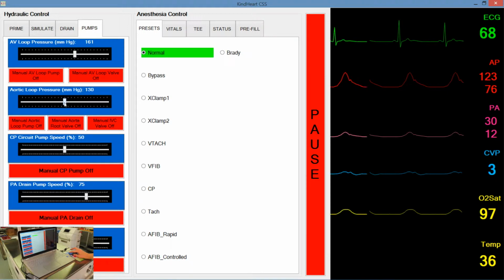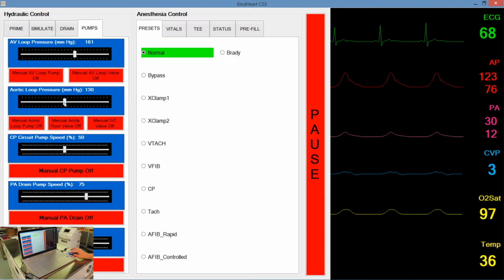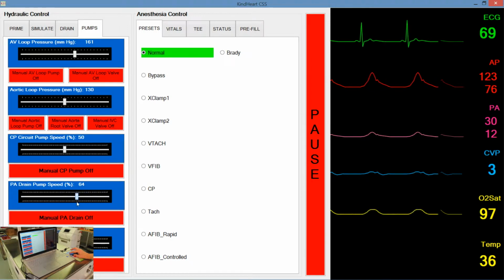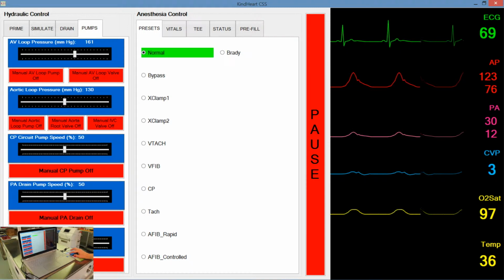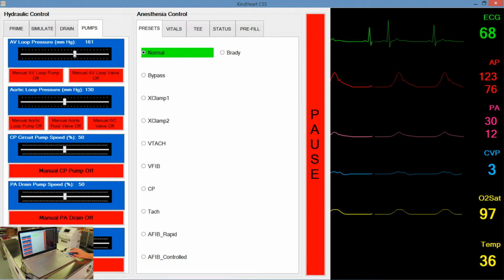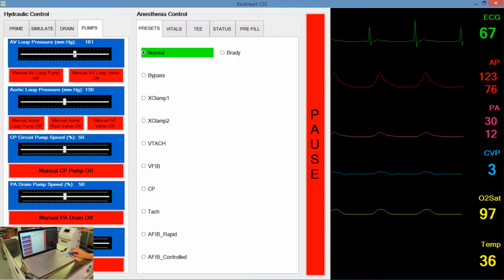What these settings do is that they make the internal pumps drive blood to achieve this kind of pressure within the hydraulic system of the device. These are not the pressures that are measured on the vital sign display screen. These pumps do a multiplicity of things, and sometimes the pressure that they need to be set at to generate an adequate pressure is higher than the number that you're going to see on the vital signs screen.